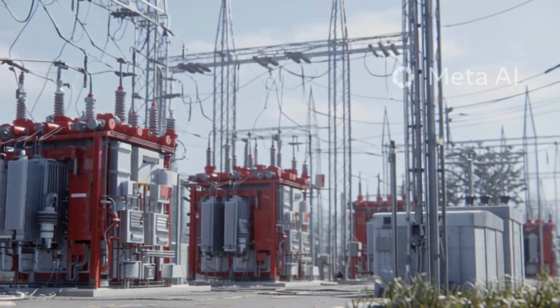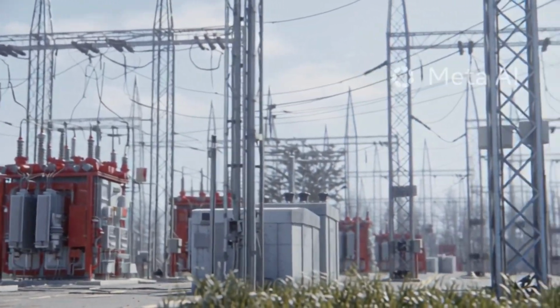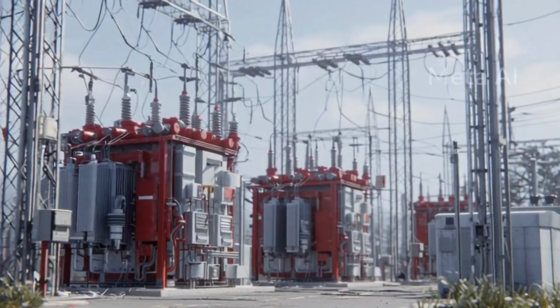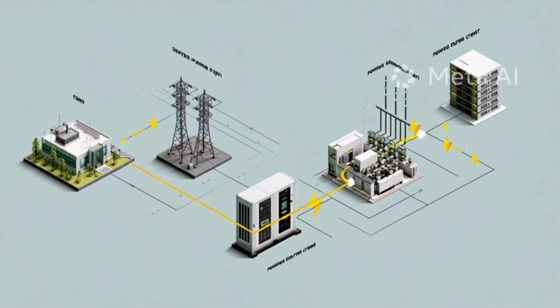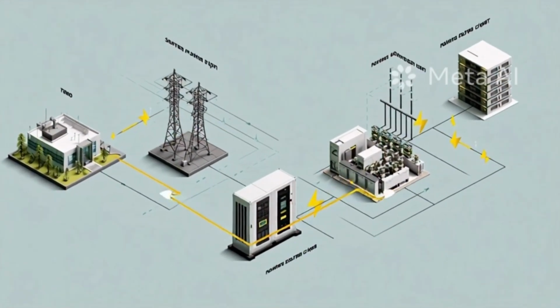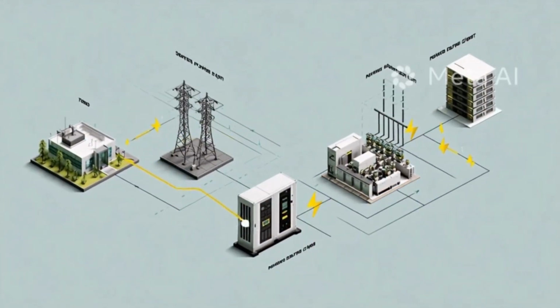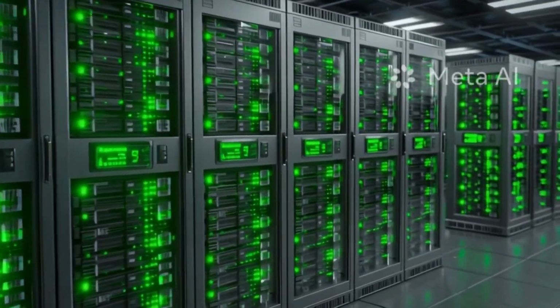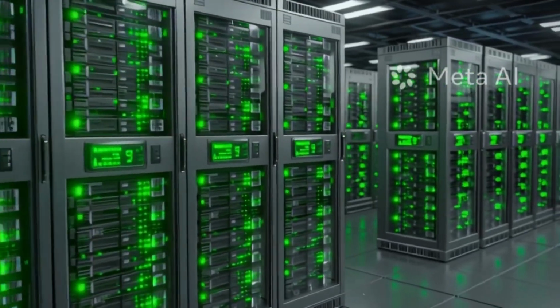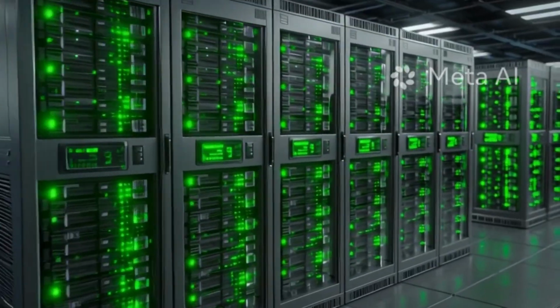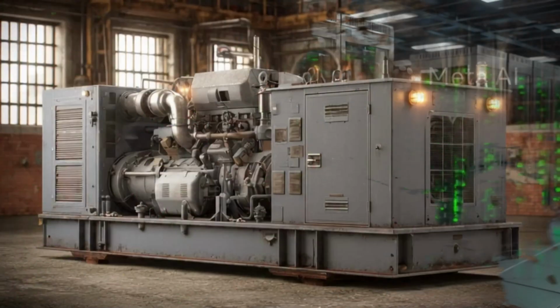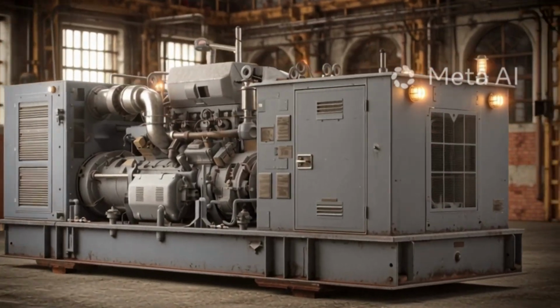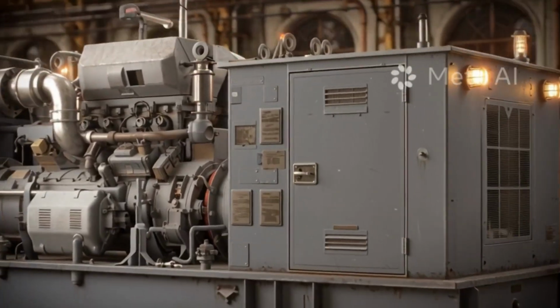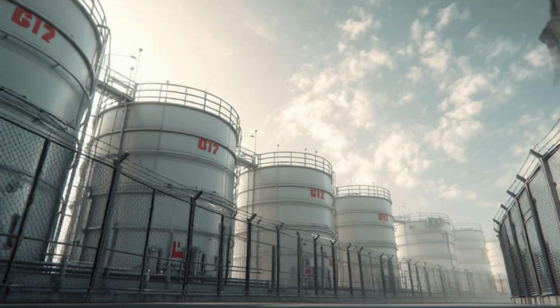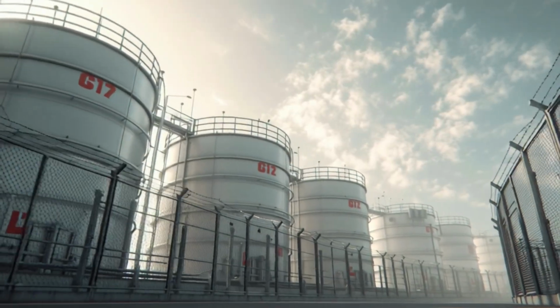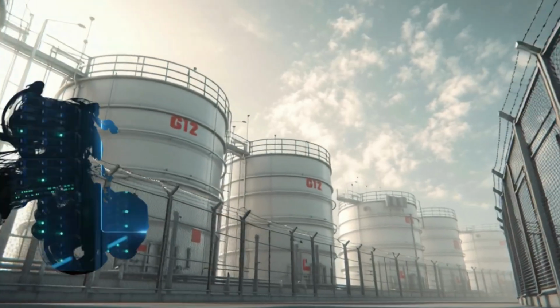A data center can never lose power, not even for a second. The power system is its lifeblood. Electricity comes in from the grid at high voltage, passes through on-site substations, and is stepped down. Uninterruptible power supplies, giant battery banks, bridge the gap if the grid fails, keeping servers running until generators start. Diesel backup generators, each the size of a truck, can power the entire facility for days if needed. Fuel storage tanks hold thousands of gallons, ensuring the generators never run dry.